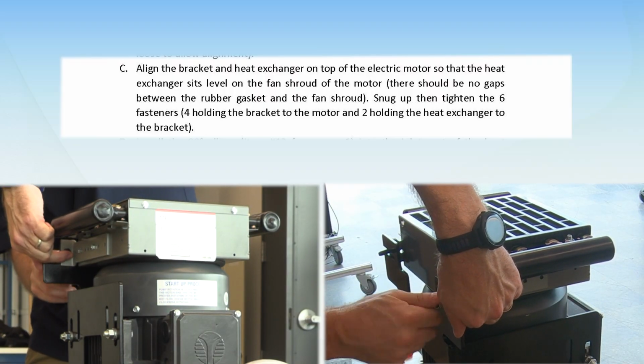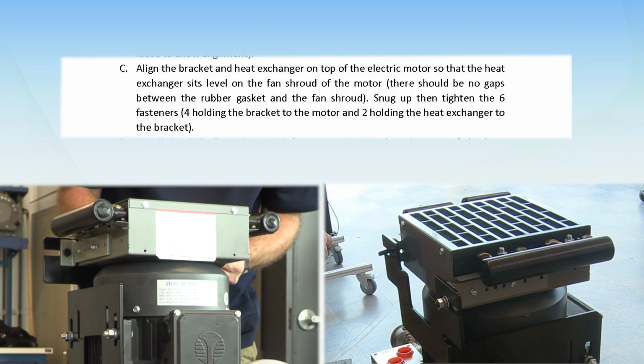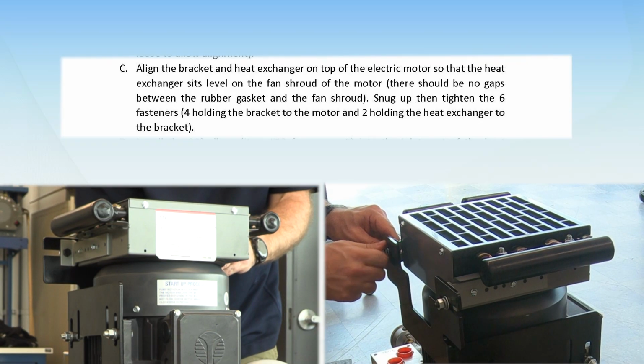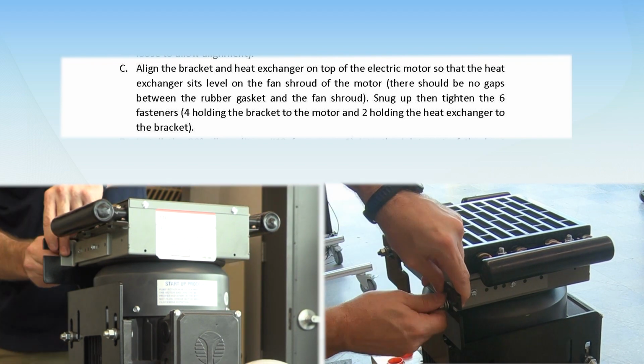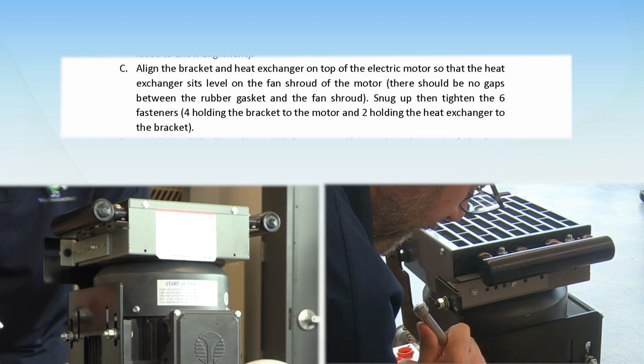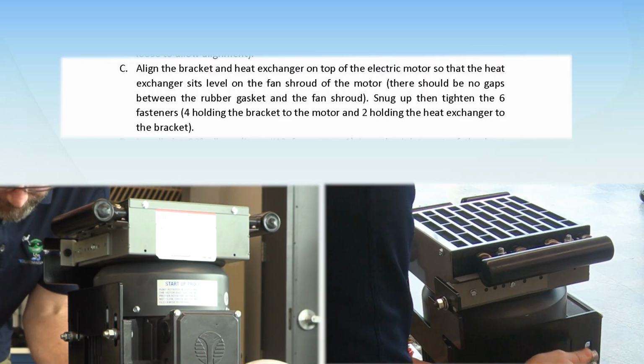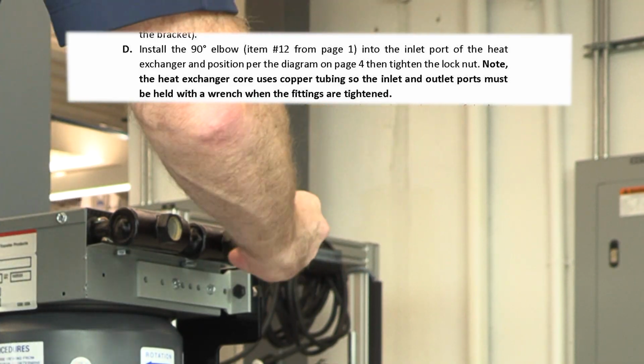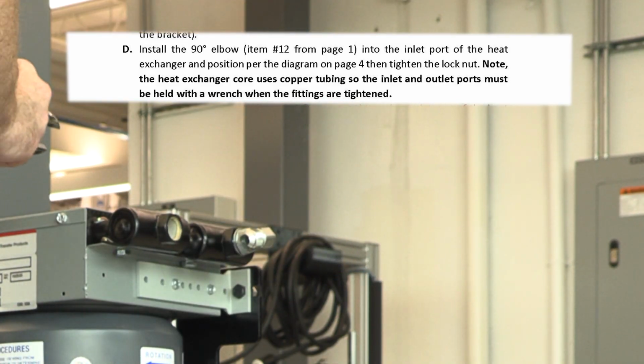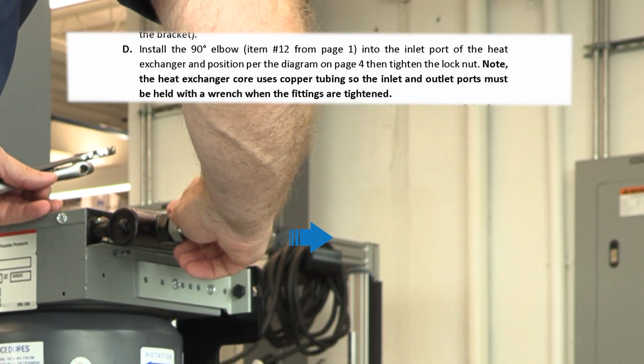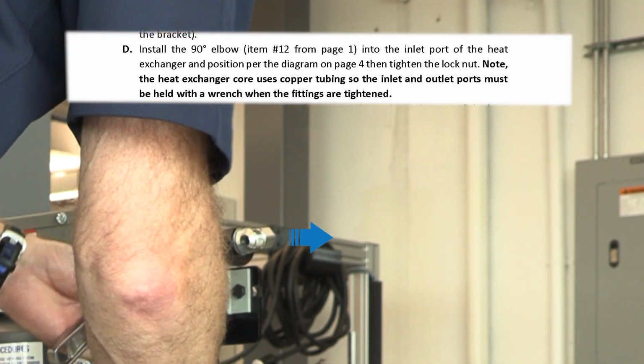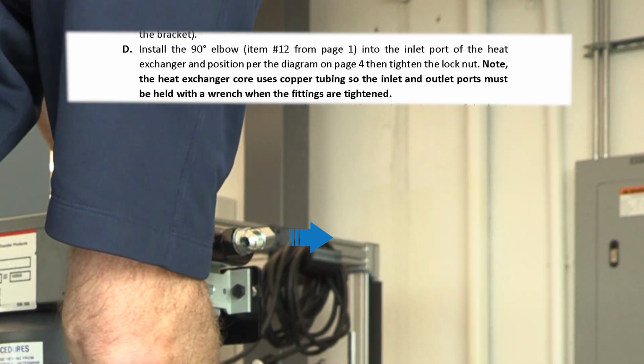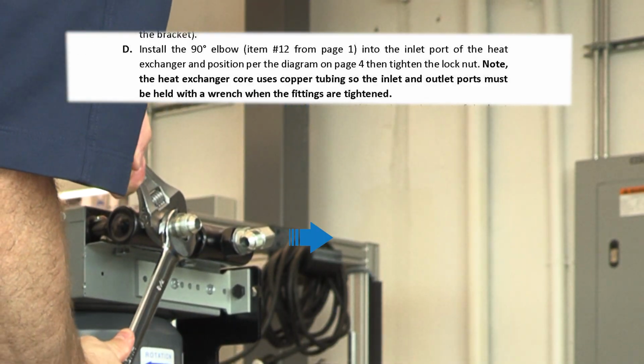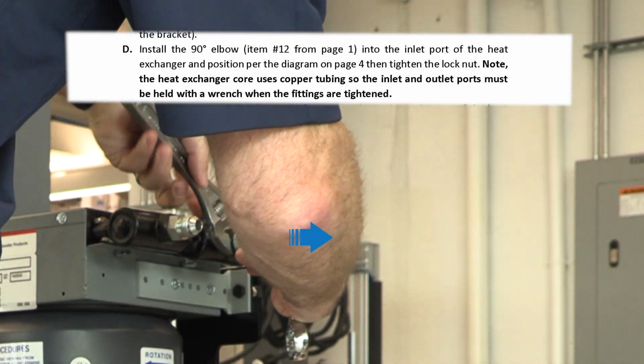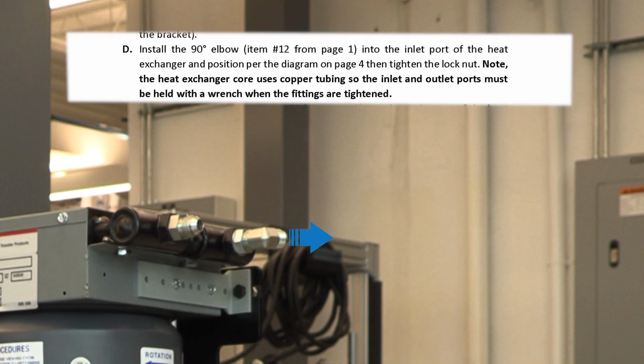Now, align the bracket and heat exchanger on top of the motor so that the heat exchanger sits level on the fan shroud of the motor. There should be no gaps between the rubber gasket and the fan shroud. Snug up, then tighten the 6 sets of nuts and bolts, securing the heat exchanger and bracket. Install this 90-degree elbow into the inlet of the heat exchanger and position so it points out the right end. Again, the heat exchanger core uses copper tubing, so the inlet and outlet ports must be held with a wrench when fittings are tight. Install the straight fitting into the outlet port of the heat exchanger. And again, be sure to hold the heat exchanger fitting with a wrench.